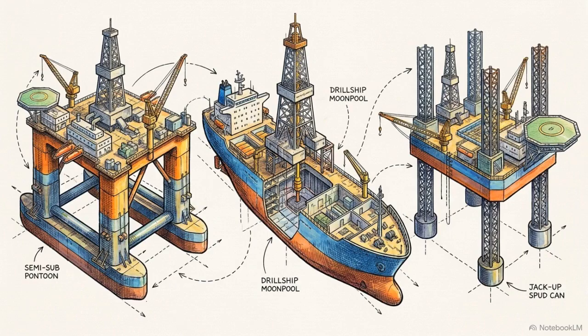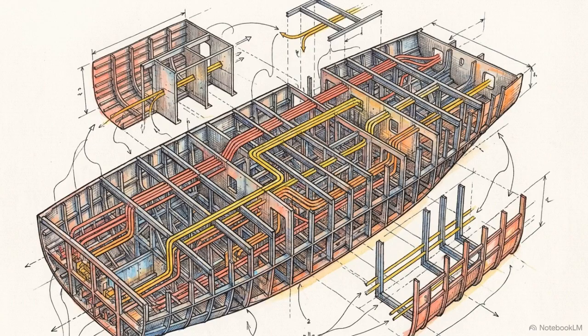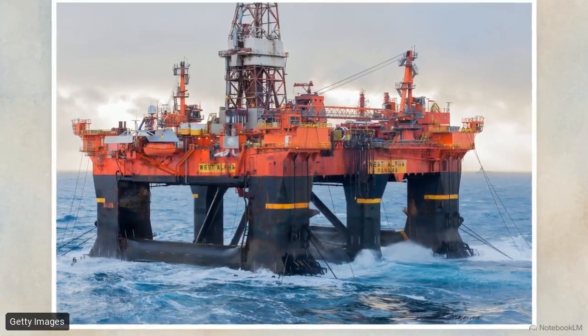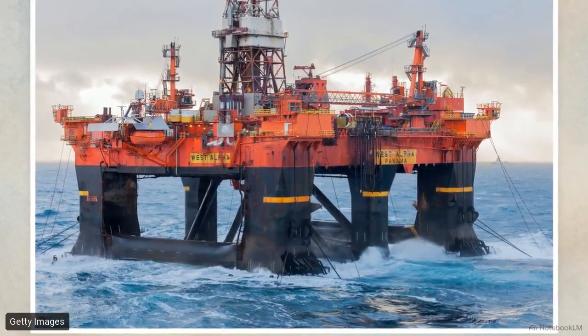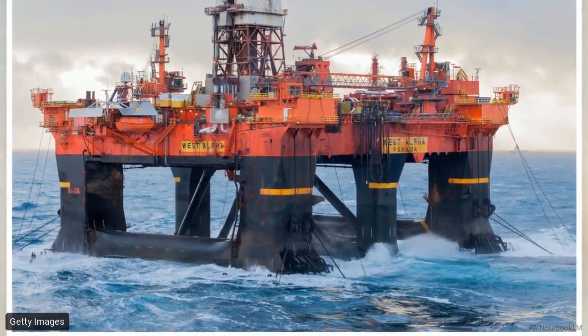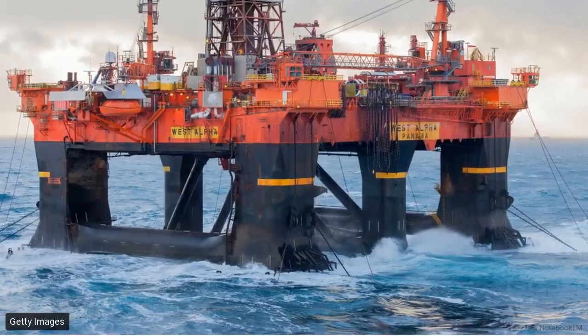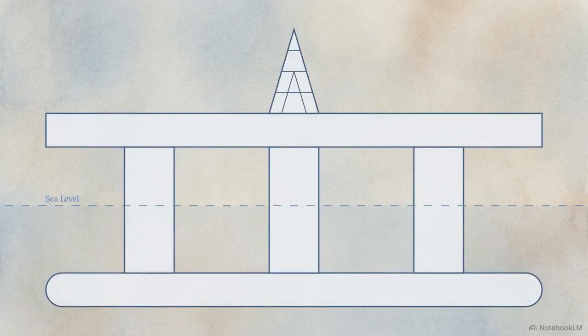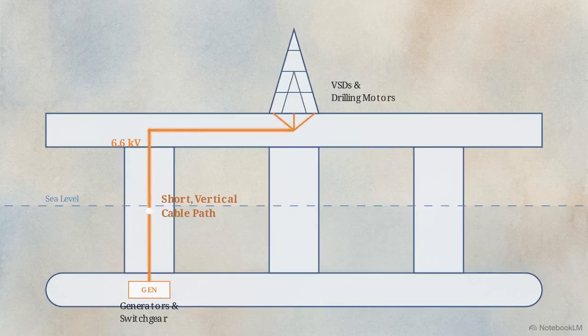Designing an offshore power system begins with the vessel's footprint. The geography of the hull establishes the fixed constraints for every cable run and switch room long before the first generator is specified. On a semi-submersible rig, heavy generators and switchgear sit low in the pontoons to maintain stability against pitch and roll. This results in power running upward through the columns, creating relatively short vertical cable paths.